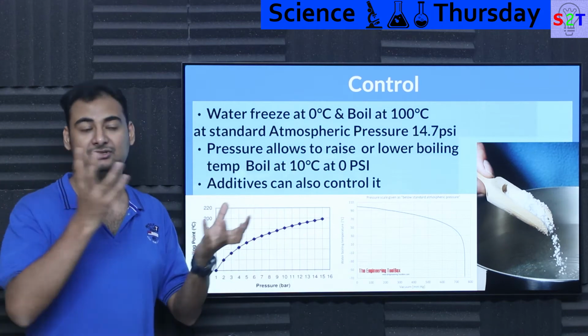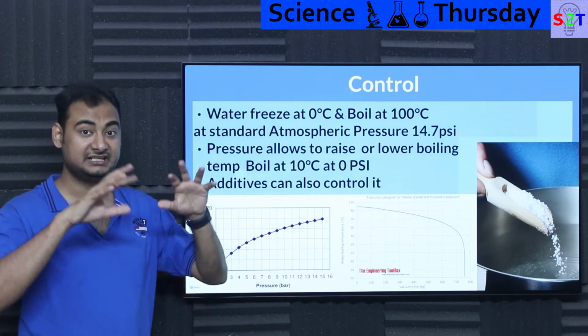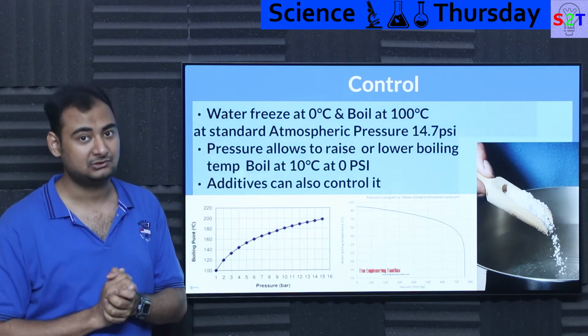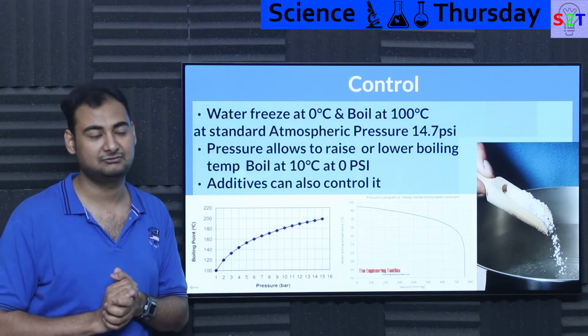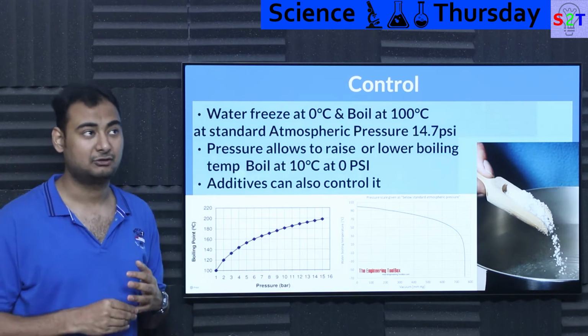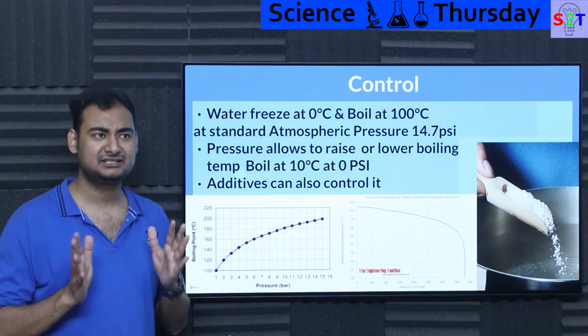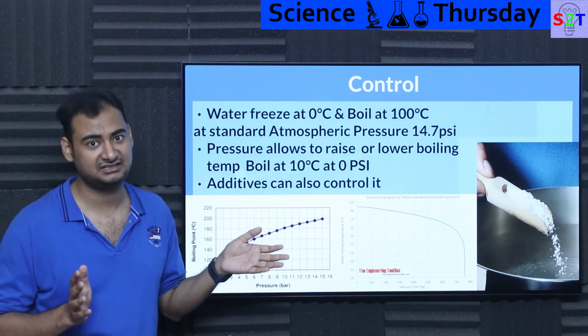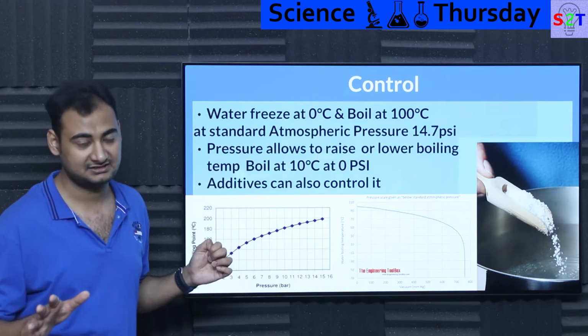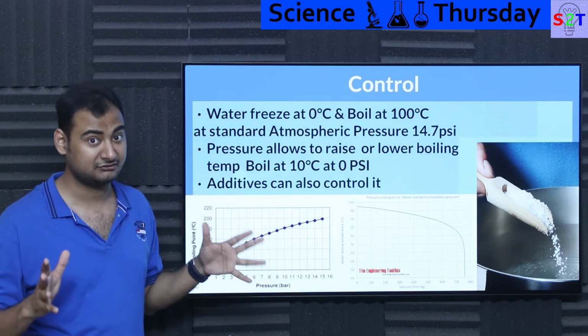So they use salt to absorb basically water moisture, create a partial vacuum, and water boils at low temperature. The benefit is you can cool the fluid. Now you can achieve cooling power of almost minus 5 degrees Celsius, some companies claim, but it's rarely achieved. You can easily achieve like 4 degrees Celsius, and that's a lot of cooling.